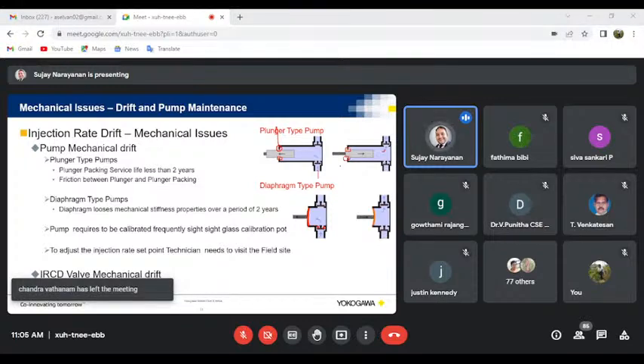Once the viscosity of the chemical changes, as I told you, the pump will not be able to handle it. So even that is creating a drift. Viscosity and density change of the chemical causes drift. That's why, if you see the data sheet or the instruction manual of the famous pump manufacturers, such as Milton Roy, very reputed manufacturers, even they say that if there is any change in the viscosity or the density of the chemical, the stroke length of the pump needs to be adjusted to maintain the set flow rate.